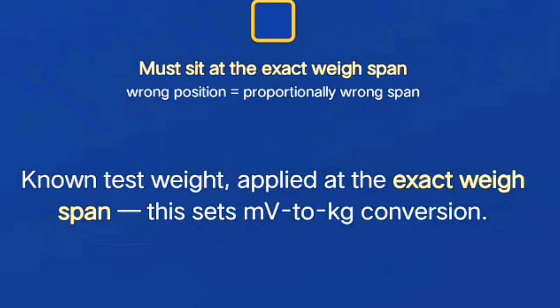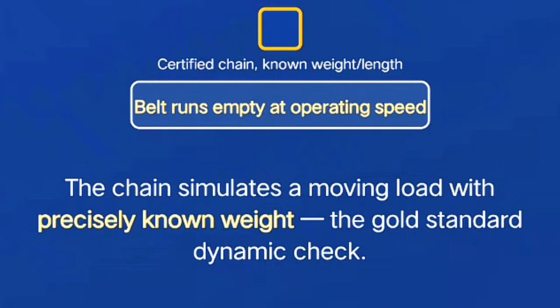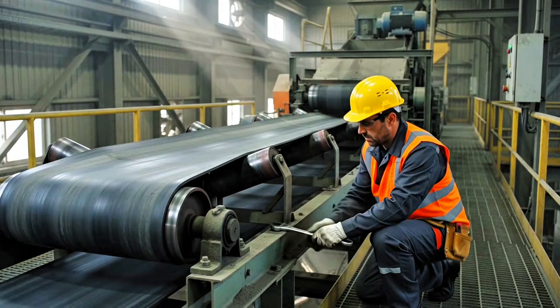The critical thing technicians get wrong here: the test weight has to be applied at the actual weigh span, the exact length of belt between the idlers that defines the weighing zone, not just anywhere on the belt. Check your feeder's manual for the specified test weight application point. Get this wrong and your span calibration will be consistently off by whatever ratio your application point is out of position. Static calibration gets you close, but it doesn't account for everything that happens with the belt actually running and material actually flowing: belt speed variation, material distribution across the belt width, and dynamic loading effects.